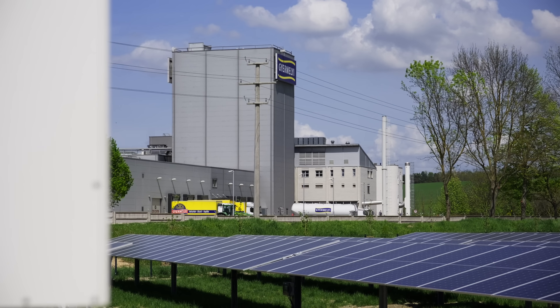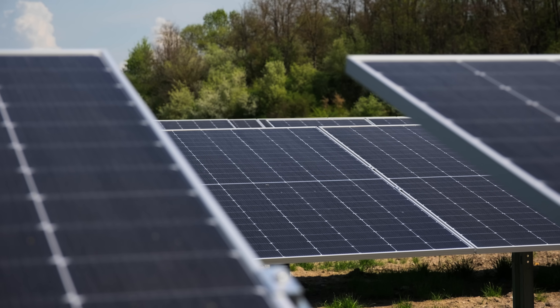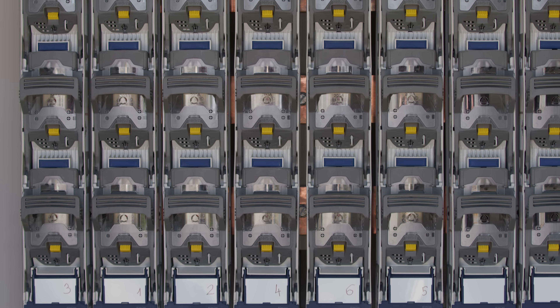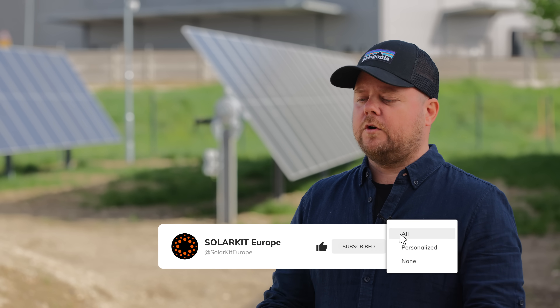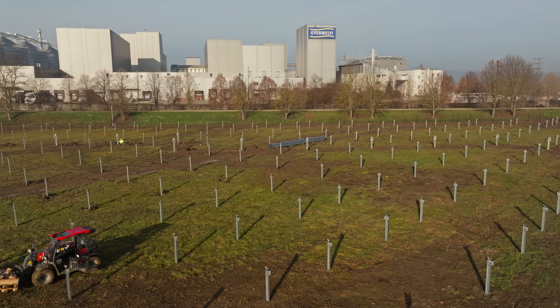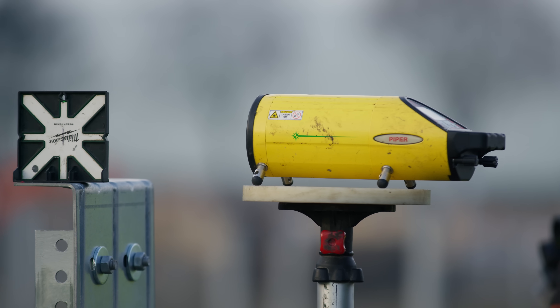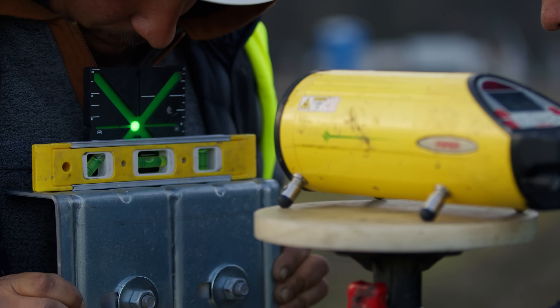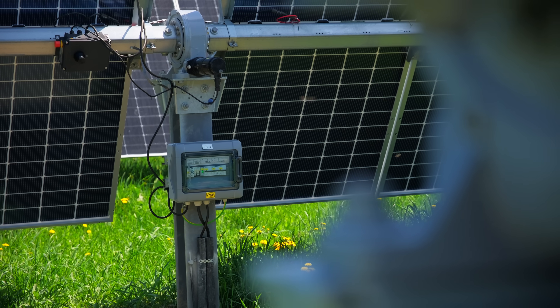SolarKit has been the largest distributor of Huawei products and Tongwei solar panels for several years now, which we're very proud of. For me, the biggest challenge in this project was the soil quality and its structural characteristics. Since all the water flows down from surrounding hills, we worked for months with geoengineers to calculate the best design, including foot density and the tensile forces we could achieve. The difficulty with this mounting system is that if a motorized foot sinks, the solar tracking system will stop rotating.